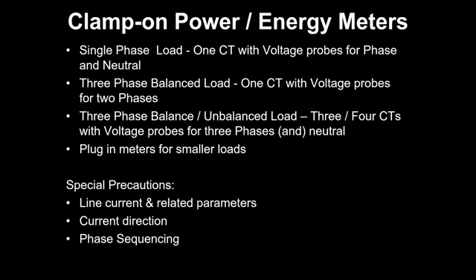And the higher-end meters have clamp-on CTs, attached and detachable, so you can have more than one CT connected to that. They are 0 to 5 ampere. There is a CT of 0 to 100 ampere. There are various CTs. So accordingly, you can make the selection for a three-phase balance load.